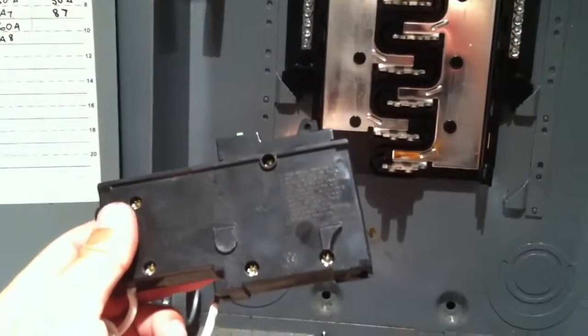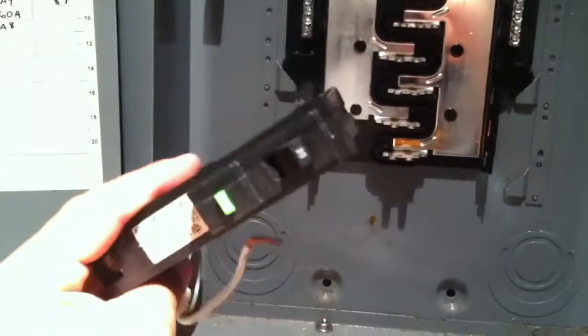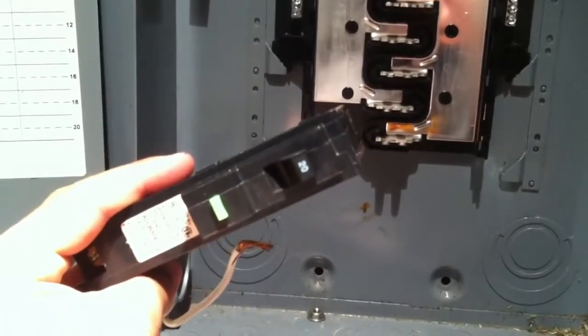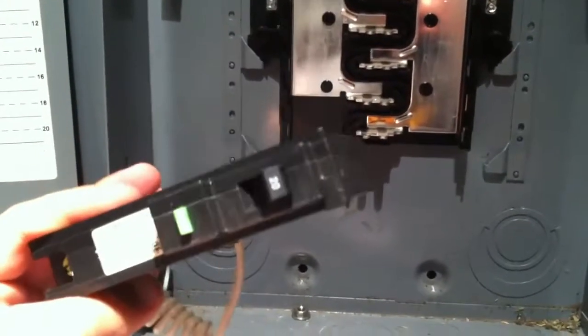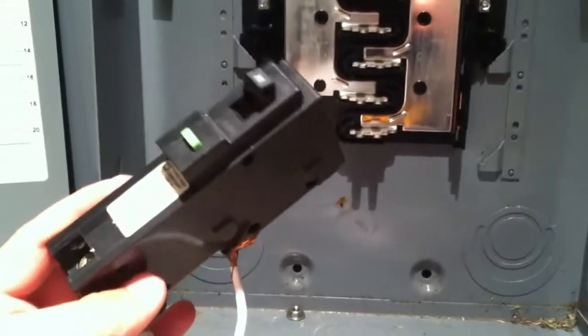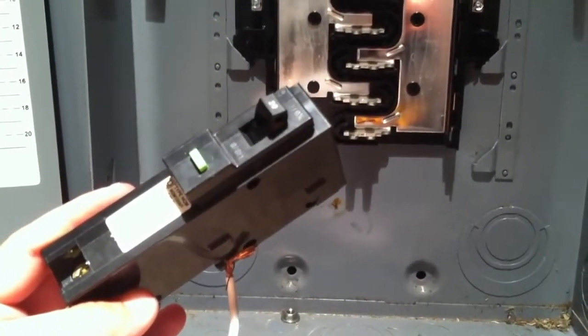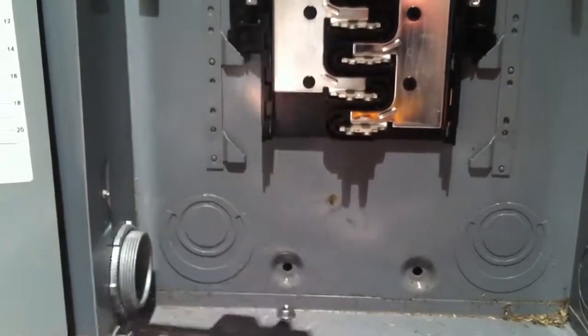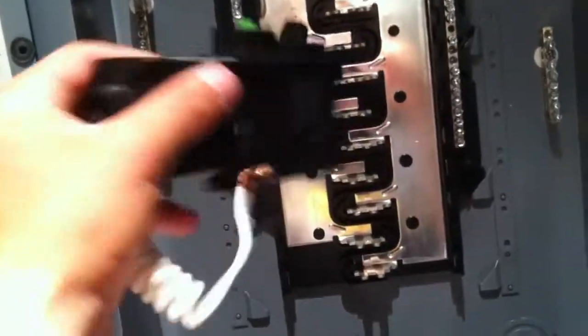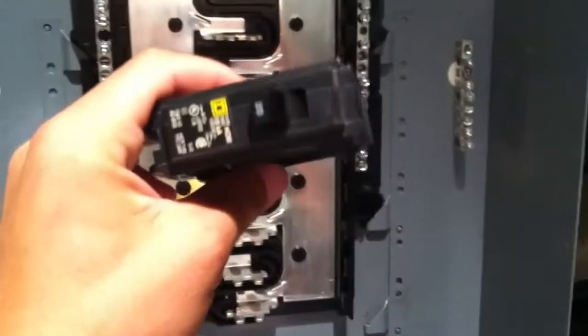So you can find these in any size. This particular one is a 20 amp AFCI. Okay, so, I mean, you can find these in 15 amp, you can find them in 20, 30, 40, 50, 60, probably all the way up to like 100. You can probably find specialty ones that go higher. This is a single pole breaker. You can find them in 2 poles, 3 poles for 3 phase. You can find them in anything, okay? So, basically, we have a 20 amp breaker here, which I discussed earlier.